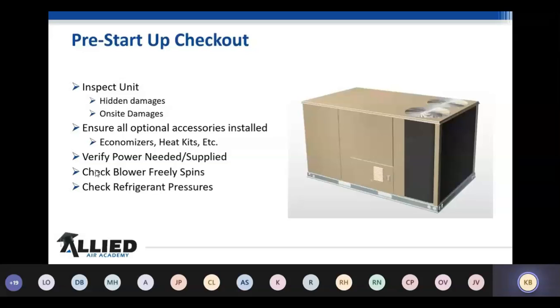Make sure all your optional accessories are installed. If you have an economizer that's put on from the factory, I would rather you put the hoods on when it's up than when you're lifting it up, because you don't know what it's going to bump into, etc. Before you even hook the crane up, verify you've got correct power and everything else. Blower spins freely, and we'll check refrigerant pressures a couple of times. Obviously, you can't check running pressures because you haven't got it hooked up, but we want to make sure there are no dead circuits or anything like that. So when we do that, you don't want to lift it on the roof at that point.